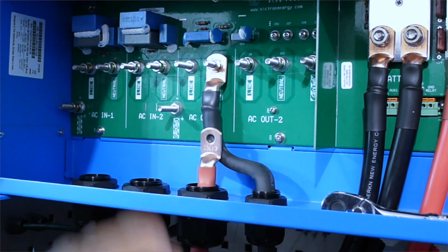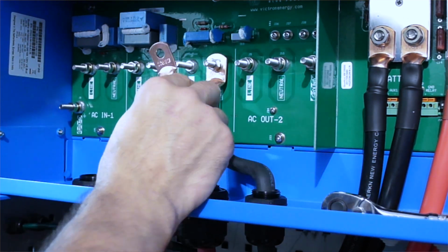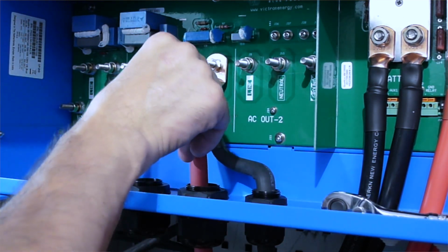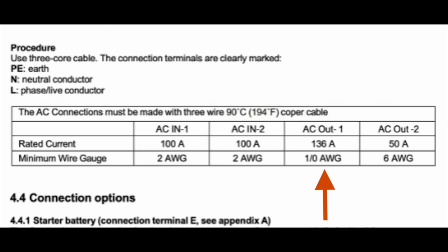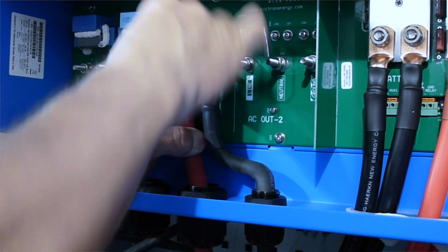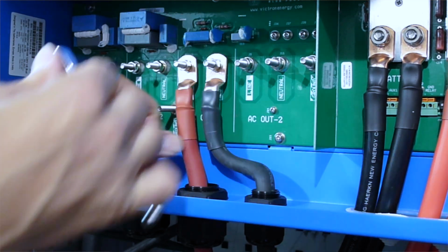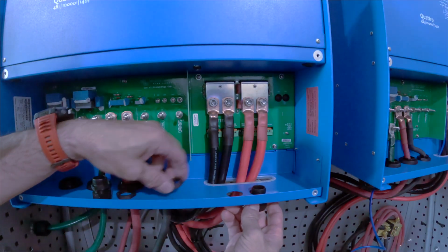Now we are going to connect the wires to the AC out terminals. The recommended size to handle 136 amps is 1 aught cable. I already have 2 aught cables, so I'm going to use that. These bolts need to be secured with a maximum 7 Nm torque.